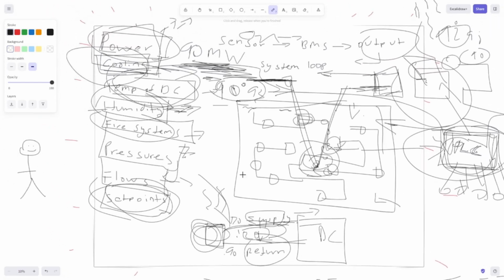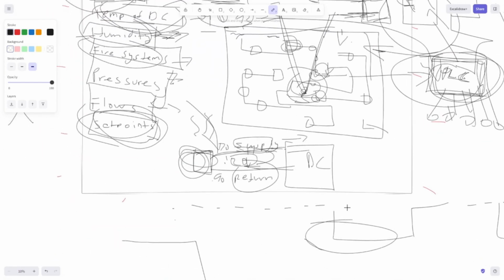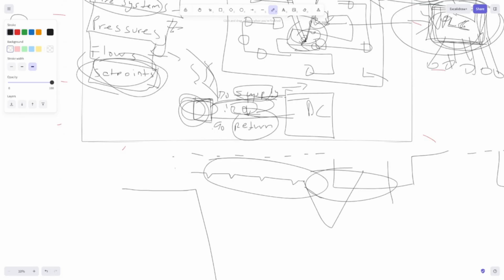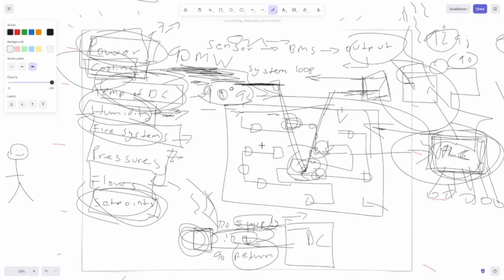And over time, trends show issues. That's what you want to notice in the BMS, because it might not even be a crazy dip. It might just be a little bit, a little bit, a little bit. But if you notice this trend, you can catch it early so it never goes down a lot. That is exactly what you use a BMS for. Because if stuff hits the fan and you were sitting on the BMS and you didn't notice, then it's kind of your fault, right? So yeah, the BMS is very important.